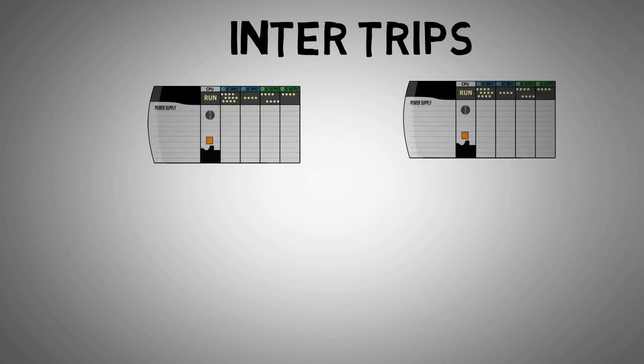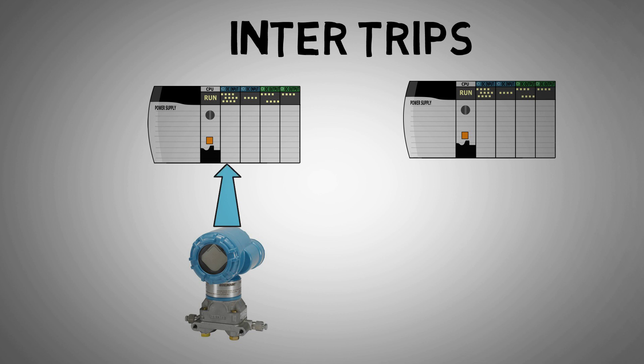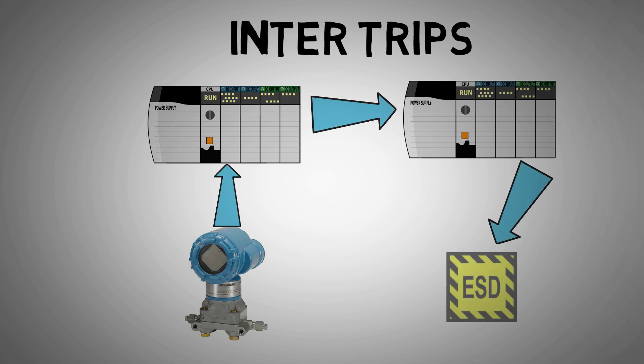A typical use case is an intertrip, where a shutdown output from one PLC becomes a shutdown input in another. This is common in larger distributed systems where separate PLCs manage individual sections of a plant.